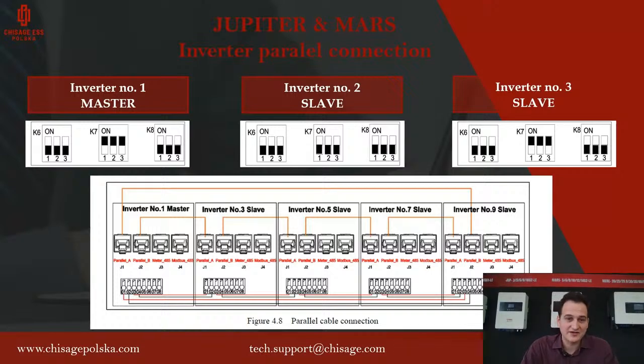Same with our RS485 cable. We connect it in ports 1, 2, 3 and 4 for our inverters. And the same, we go from first to second to third to the last, and from the last to the first inverter, to make sure we have the backup for this communication. And then we have the switches on our inverter, K6, K7, and K8, for parallel communication.